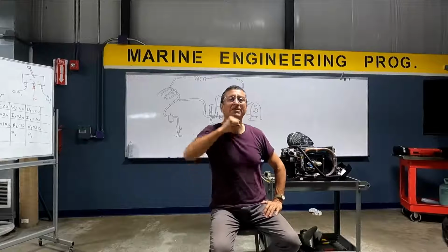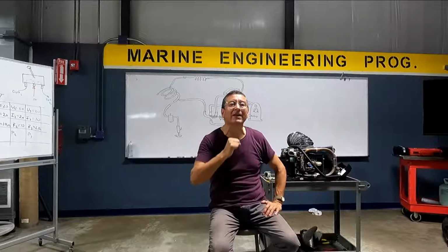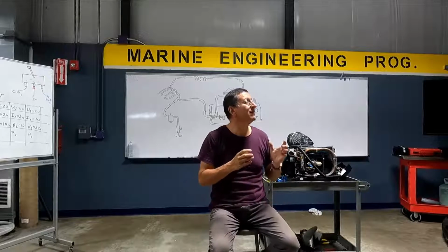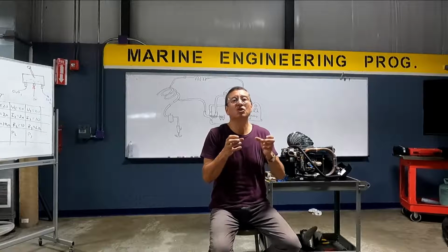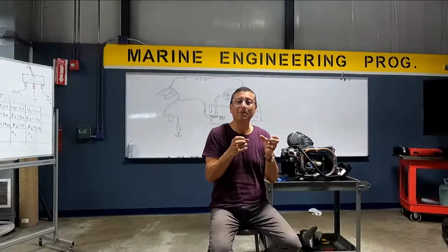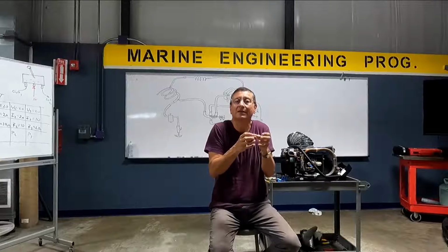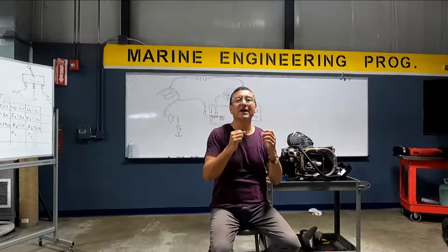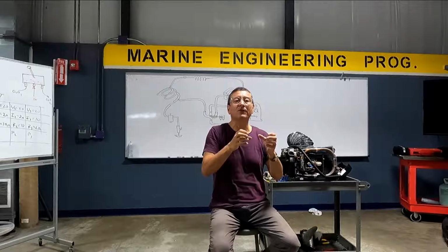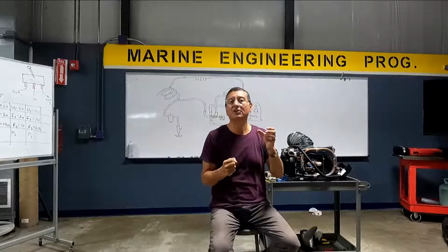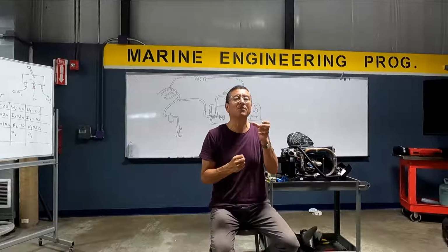It's hard for that piston to start at the beginning. For that reason, the system uses 2 capacitors together to jump it. Immediately the compressor starts to move, the start capacitor disconnects and it continues running only with the run capacitor.